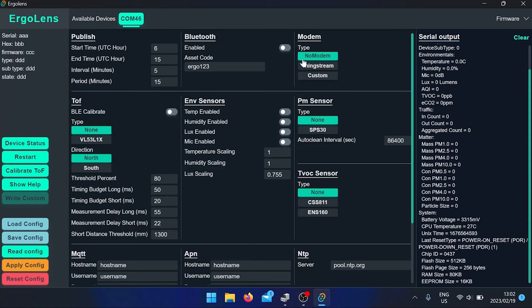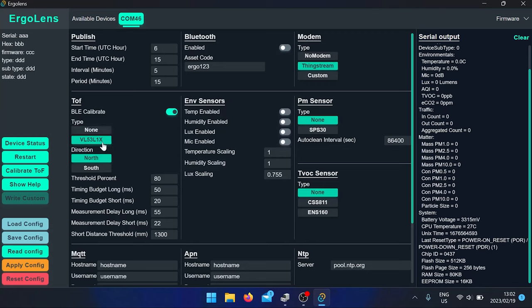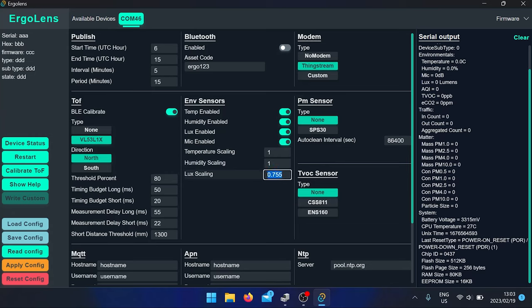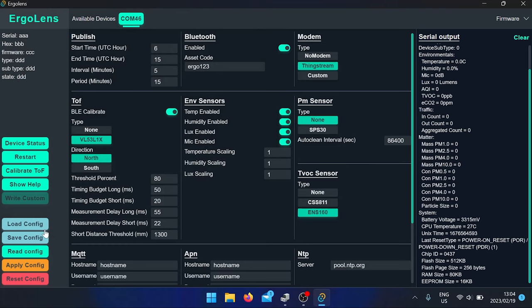I will now show you how to make a config. First click on Thingstream. Turn on the setting to be able to calibrate the device from your phone. TOF north. Turn the TOF sensor on. Enable the environmental sensors. Make sure the scaling values are all one. Turn on the ENS sensor, enable the Bluetooth, and then proceed to save the config to use in the future. This configuration is already on the device when you receive it.